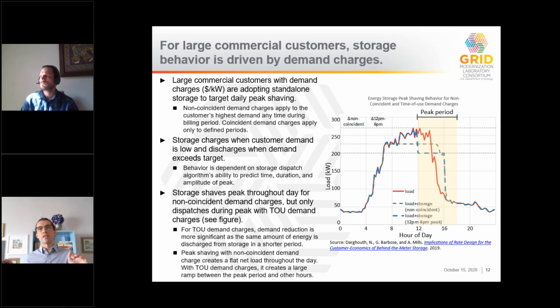a uniform peak shaving. However, with the time of use demand charges, which is that peak period range you see, storage only dispatches during the peak period. Since the storage system has a fixed amount of energy, the discharge during the peak is much deeper than with the non-coincident demand charges. But because storage waits to discharge until the peak, a large ramp occurs between the peak period and all other hours. So both of these structures have net load impacts that could be desired by a utility, but their impacts certainly are not the same. So let's go to the next slide to summarize storage.